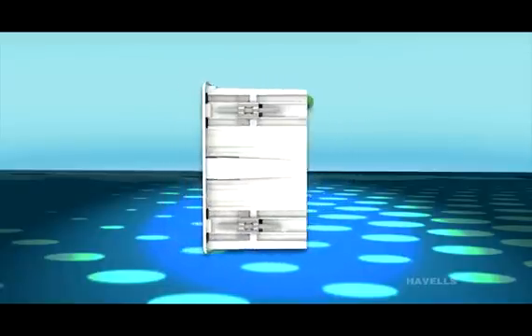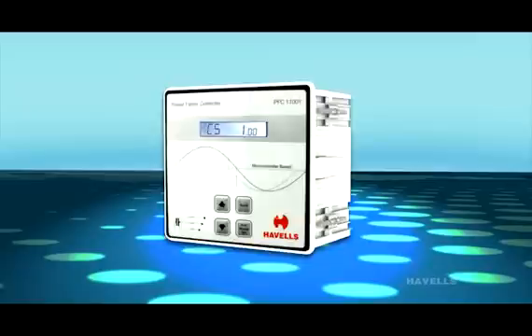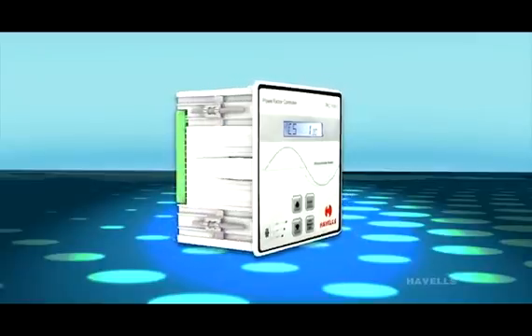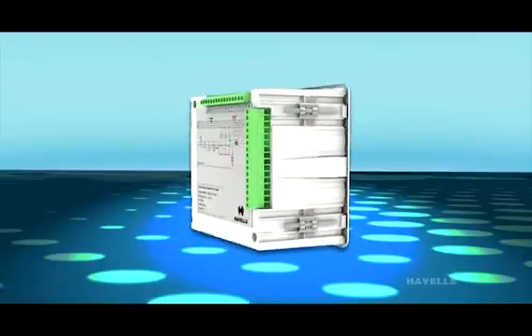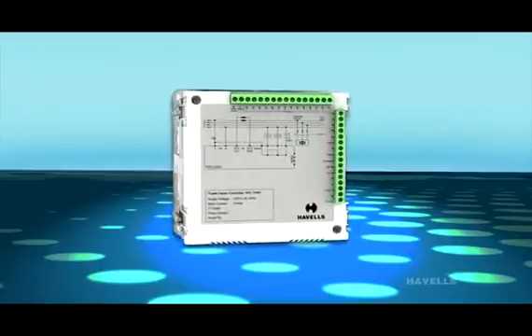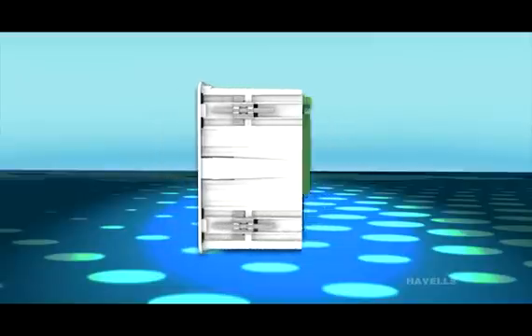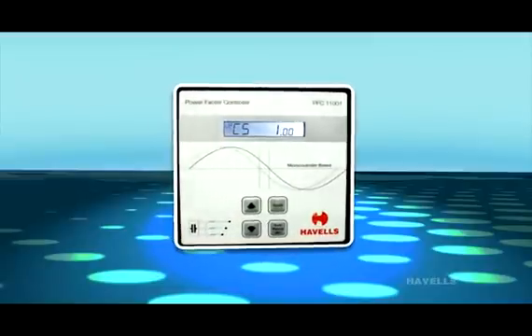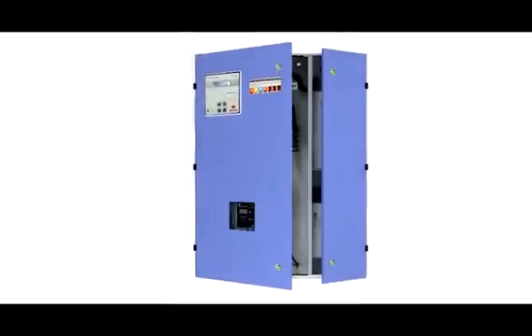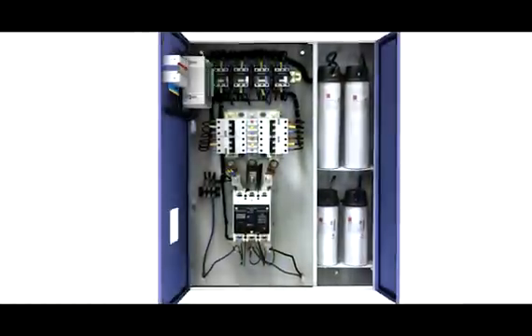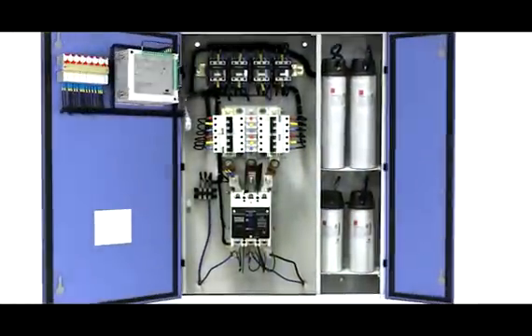capacitor stages are switched in and out by the APFC relay. The contactor control logic is optimized so that the desired power factor is achieved with minimum switching operations, thus ensuring an optimized life cycle of the capacitor bank.